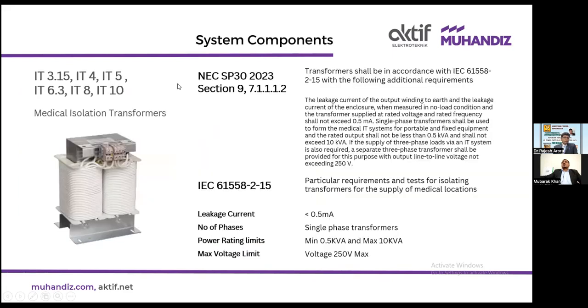Okay. Coming to the isolation transformer, this is not a normal transformer which we see around. This is a special transformer which has special requirements as per IEC 61558-2-15, and the NEC standard, the Indian standard, clearly says that the transformer shall be in accordance with IEC 61558-2-15. So the NEC standard says the transformer should comply with the IEC standard. That is why the IEC standard becomes applicable for the medical isolation transformer. They come in various sizes, right from 3.15 kVA to 10 kVA. Okay. The key requirements as per the IEC standard are that the leakage current from phase to phase, phase to ground, primary, secondary must not be more than 0.5 milliampere.